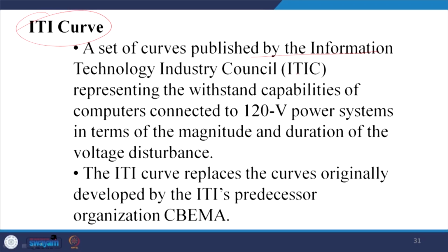It represents the withstanding capabilities of computers connected to 120 volt systems in terms of the magnitude and duration of the voltage disturbance. The ITI curve replaces the curves originally developed by ITI's predecessor organization.